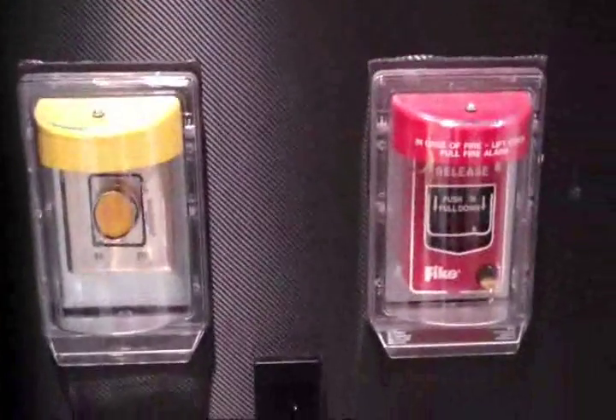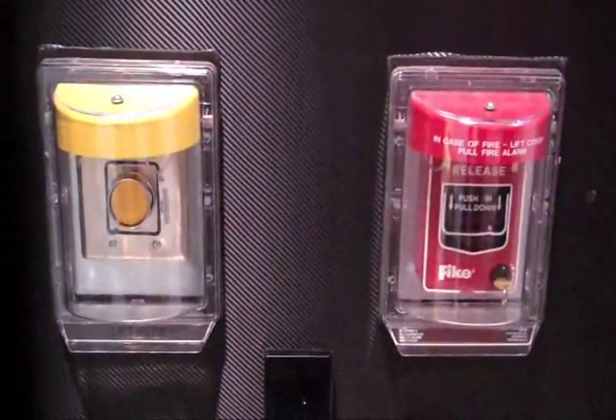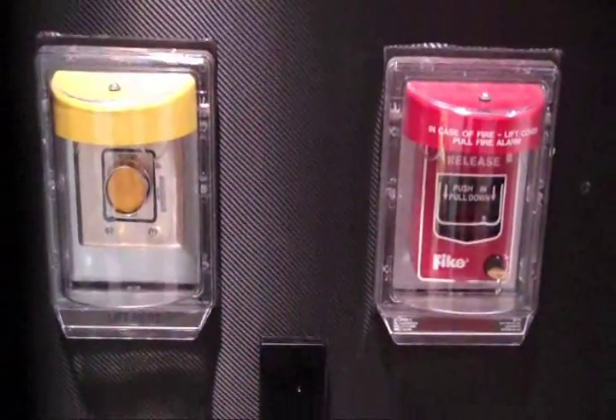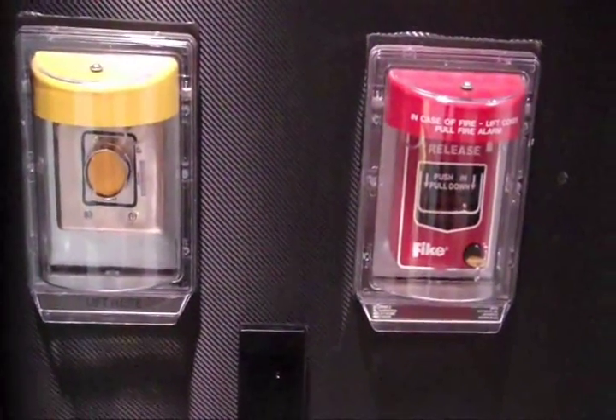Exiting the end of the module, we'll turn around and go back through what is the hot aisle. You can also see on the external of the module, we have full security, fire suppression, and access controls built into each individual module and controlled independently in each module. So from a logical perspective, each one of these modules is its own compartmentalized 200 kW data center that you can upgrade concurrently, maintainably, from 200 to well over 500 kW in the same footprint.